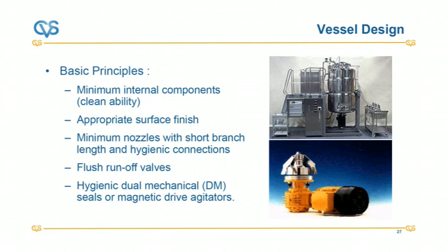So a little bit about vessel design. There's a magnetic agitator there at the bottom. But basically for hygienic design, not always possible in certain fermenters, we want minimal internal components, appropriate surface finish, minimum nozzles or portals with short branch length and hygienic connections, and flush runoff valves, so that we've got a runoff valve flush to the line of the tank itself. We also need the right level of seals where we've got shafts for agitators, and where we've got drives on pumps. We want some kind of dual mechanical seals or magnetic drives or agitators.